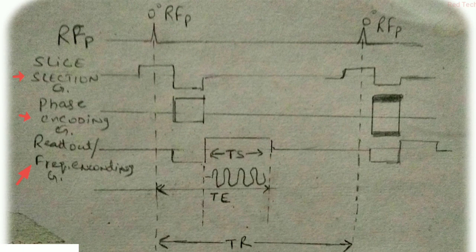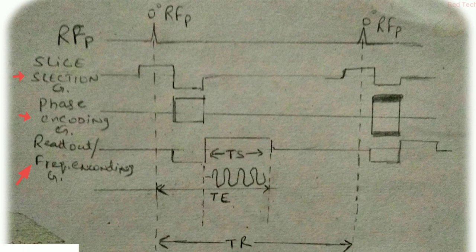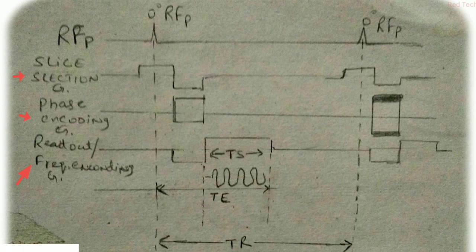In the earlier videos we have studied about the spin echo modification and others. In that sequence, basically the 180 degree or 90 degree RF pulses are used, but this is typically different from them. In this we use only an angle which lies between 10 to 80 degrees.